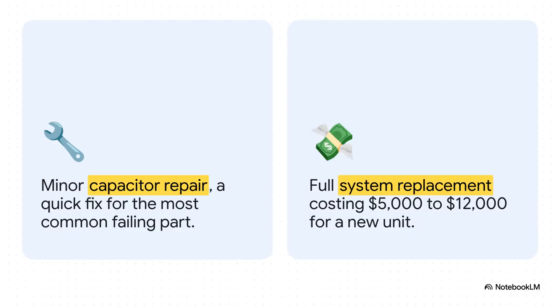Okay, let's look at the financial stakes here. This really highlights why proactive maintenance is absolutely crucial. A minor capacitor repair, that's a quick, inexpensive fix for a part that frequently fails in extreme temperatures. But if you ignore the warning signs, like a strange humming sound or hard starts, that failing capacitor ends up damaging the compressor itself, and suddenly, boom, you're facing a full system replacement, costing anywhere between $5,000 and $12,000. A cheap fix literally prevents a massive financial emergency. Talk about a huge return on investment.